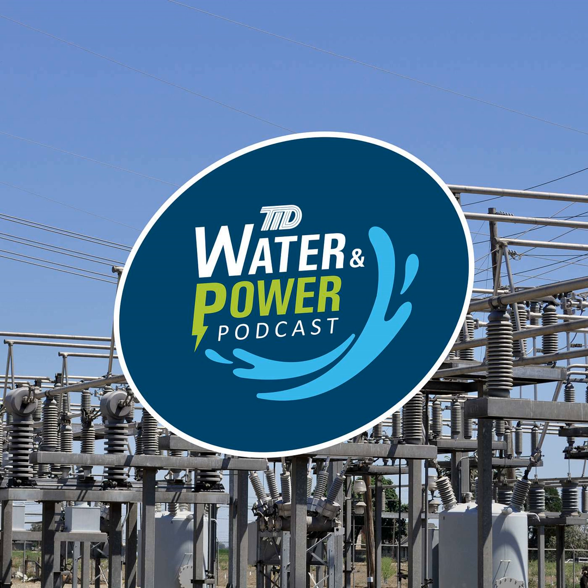So we went about procuring the transformers. We also had to change the spacing in the substation to allow for them, since they were pretty close together, so we had to spread those out in order to fit them. We also wanted to add protection to the high side and low side of those transformers, which allowed us to put in a differential scheme—the fastest and most sensitive type of protection you could get.